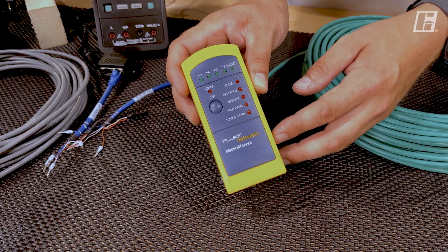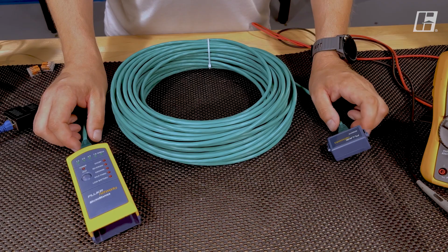We're going to test it with the Fluke Micro Mapper. The brand isn't important. Any of these tools do essentially the same thing. They're going to check all of the pairs as well as the shield. We're going to connect both ends. The nice thing with this is one end can be far away in the field. I believe this one works to about 200 meters, but you'll have to check your specific tool. I set it to cable mode and press the test button. We can see that we have continuity through all of them and no crossed over wires.